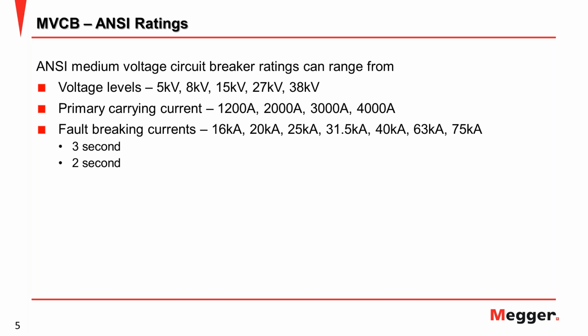So if you see 16 kA, 3 seconds, it means the breaker can carry that high current for only 3 seconds. Otherwise, the breaker will be broken. Okay, just a moment.